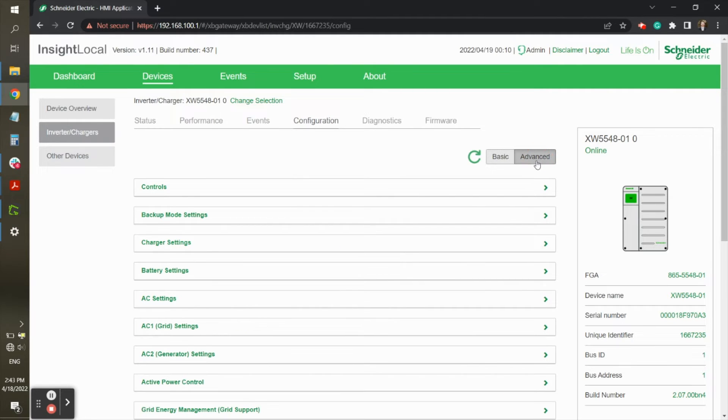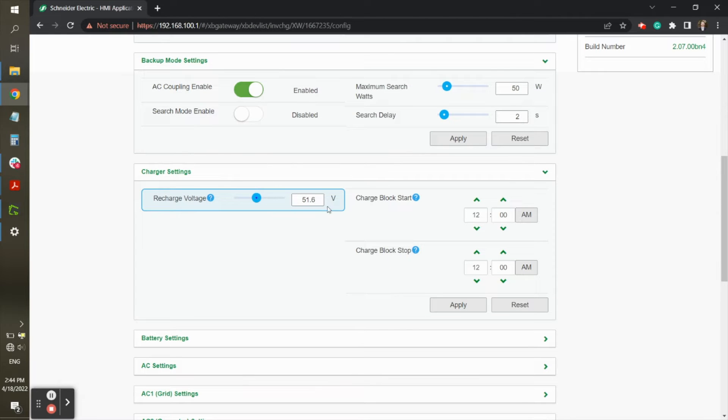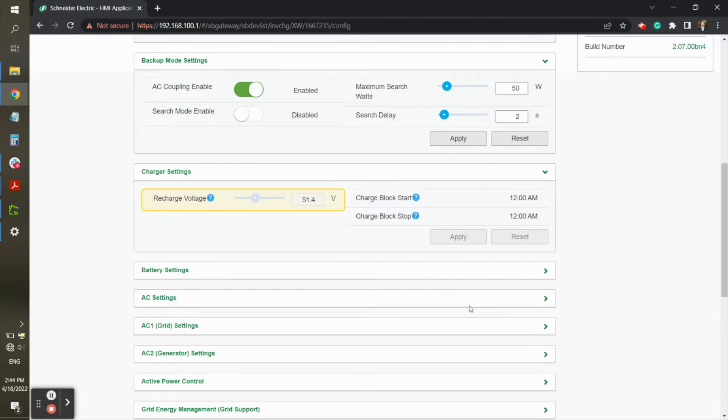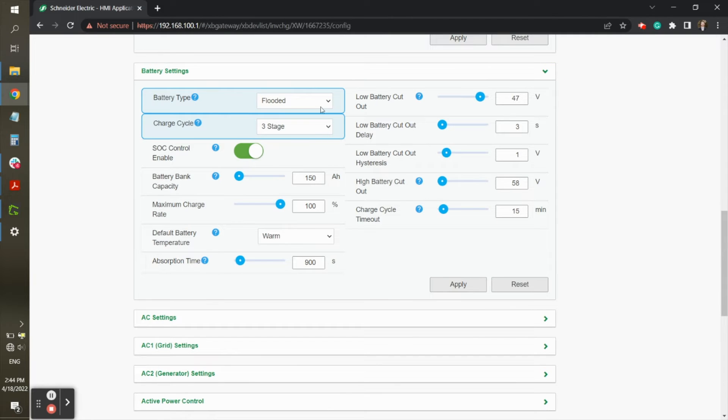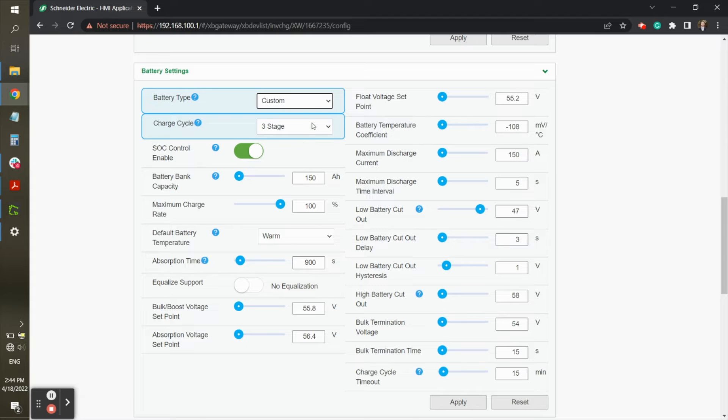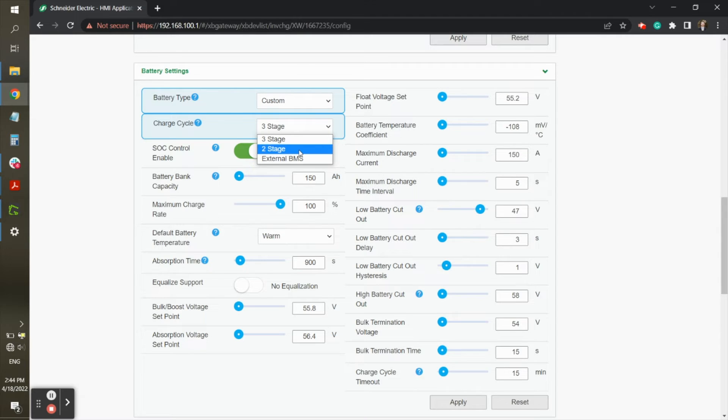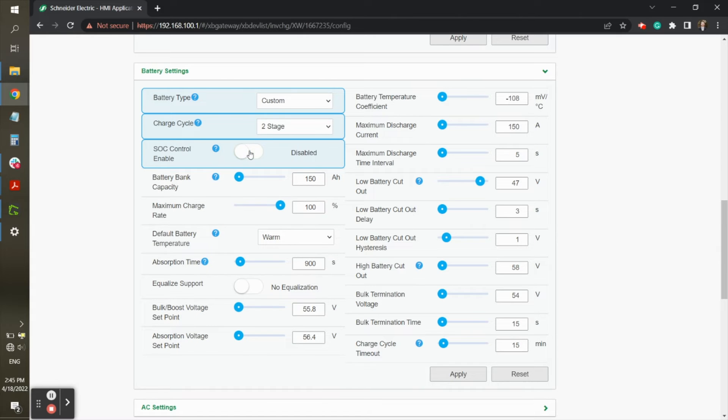Under Charger Settings, Recharge Voltage can be set to 51.4 volts for roughly 80% depth of discharge. This can be adjusted to a higher voltage if so desired. Under Battery Settings, you will want to set Battery Type to Custom and Charge Cycle to 2 stage, which effectively disables the float charge.